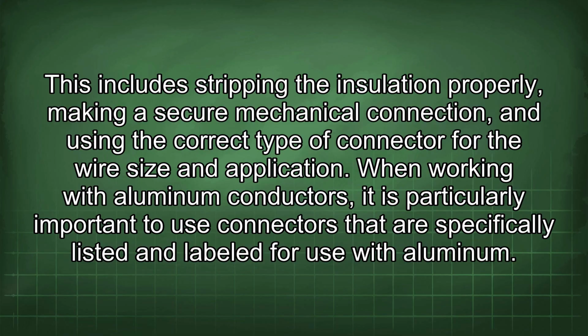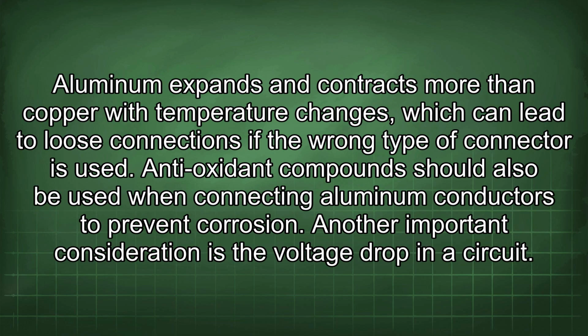When working with aluminum conductors, it is particularly important to use connectors that are specifically listed and labeled for use with aluminum. Aluminum expands and contracts more than copper with temperature changes, which can lead to loose connections if the wrong type of connector is used. Antioxidant compounds should also be used when connecting aluminum conductors to prevent corrosion.